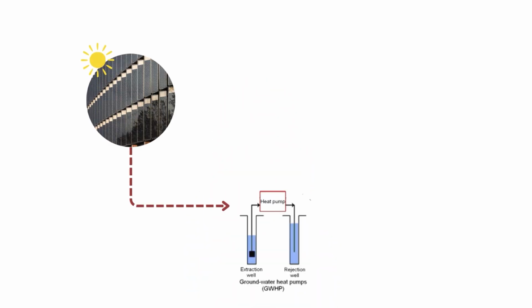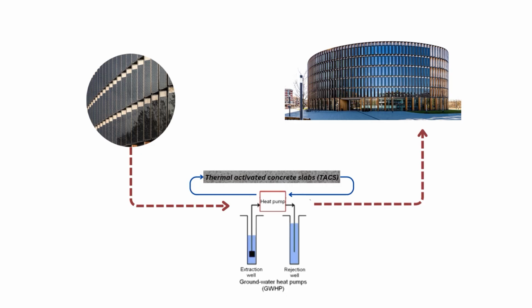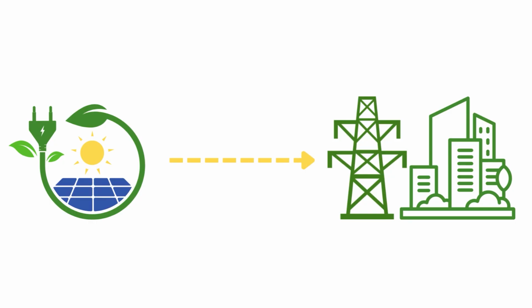Now, let's connect the dots. The building's two main systems, the solar skin and the geothermal heat, work in perfect synergy. During the day, BIPV panels generate electricity that powers the heat pumps. The heat pumps, in return, use the electricity to heat or cool the building using groundwater. Because the panels produce the most power when the building is most active, the system achieves a natural balance between supply and demand. Whenever solar generation exceeds usage, the surplus electricity is fed back into the public grid, offsetting the small amount of power the building imports in darker months.